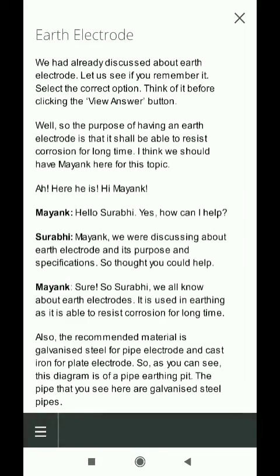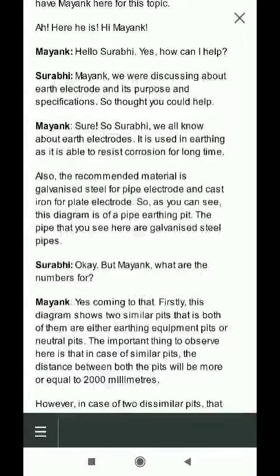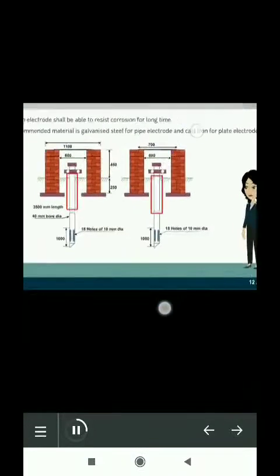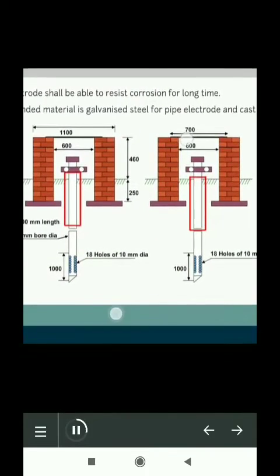Sure. So, Surabhi, we all know about earth electrodes. It is used in earthing as it is able to resist corrosion for a long time. Also, the recommended material is galvanized steel for pipe electrode and cast iron for plate electrode. So, as you can see, this diagram is of a pipe earthing pit. The pipes that you see here are galvanized steel pipes.